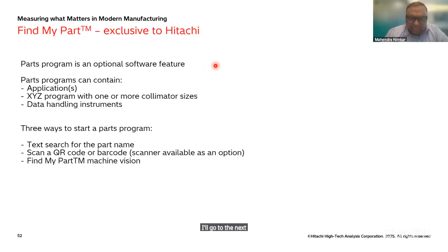I mean, what application you selected, let's say it is zinc on ferrous, what the collimator size was, and other settings, it all gets stored automatically. Next time you put the same sample in the instrument, it automatically detects that it's the same sample. Once it pops up, if you say yes, it's the same type of sample, the instrument will start analysis immediately. So you need not select the application or collimator or other settings again. This saves a lot of time. If you are doing the same or a similar sample again and again, this is a very important feature.